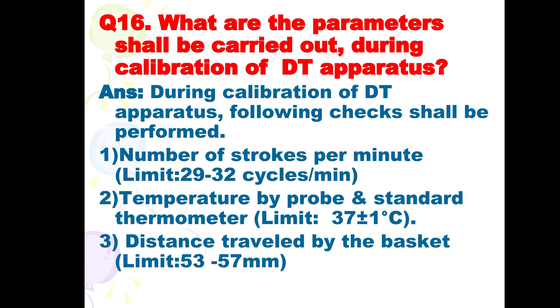Next is: what are the parameters to be carried out during calibration of the DT apparatus? During calibration of the DT apparatus, the following checks shall be performed: number one, number of strokes per minute; number two, temperature by probe and standard thermometer; and number three, distance travelled by the basket.